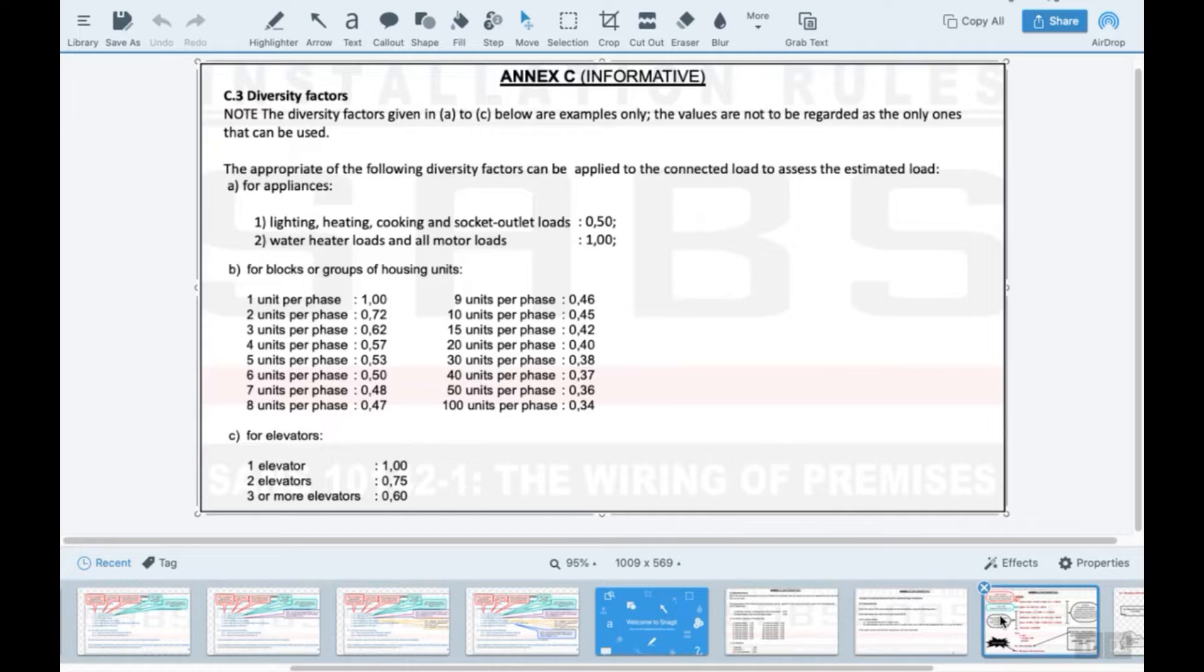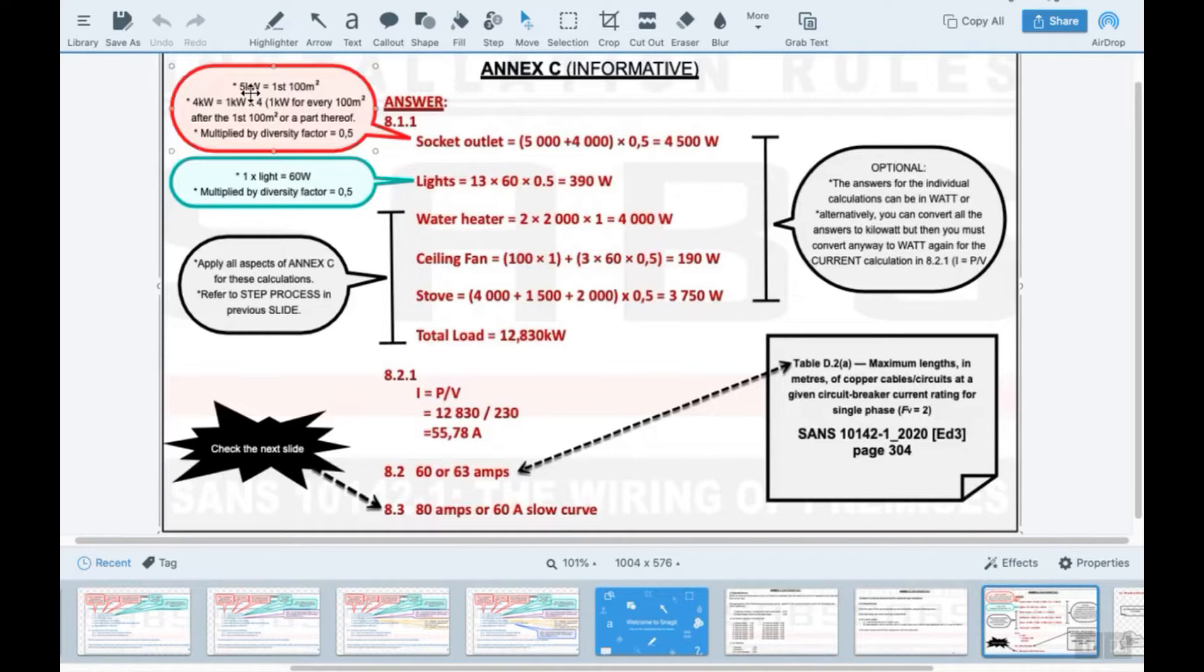That is for plugs. Where do we find that? What does it look like? It says five kilowatt for the first hundred square meter, then it would be four kilowatt, which means one kilowatt for every hundred square meter and a part thereof. So the part thereof would be the nine point whatever it was, and then multiplied by the diversity factor.